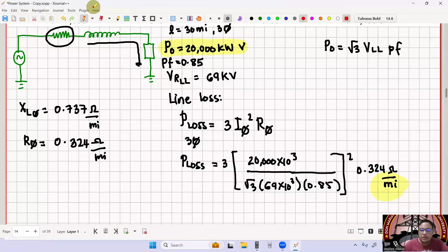Take note, output power is square root of 3 multiplied by line-to-line voltage multiplied by power factor. So power equals 20,000 kilo over square root of 3 times 69 kV times power factor 0.85, the quantity squared, multiplied by R per phase, which is 0.324 ohm per mile. But since it's still per mile, we multiply by the length to get the total watts — times 30 miles — so the mile units cancel out.